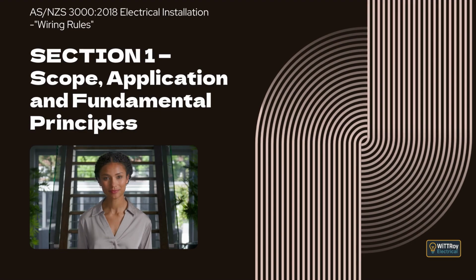Clause 1.4.3 is accessible, readily. This means it can be reached quickly, without climbing over things or removing obstructions, and without needing a movable ladder. It also means the item must not be more than 2.0 meters above the ground, the floor, or the platform. Clause 1.4.4 is accessory. This includes devices such as switches, fuses, plugs, socket outlets, lamp holders, adapters or ceiling roses that are part of wiring, fittings, luminaires, switchboards, or appliances. It does not include the lamps, the luminaires, the appliances, or the switchboards themselves.